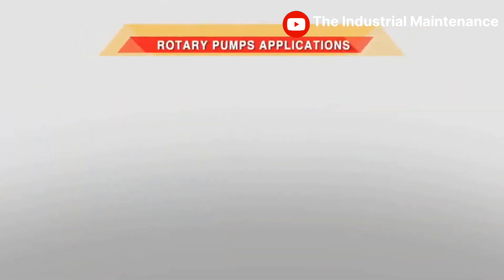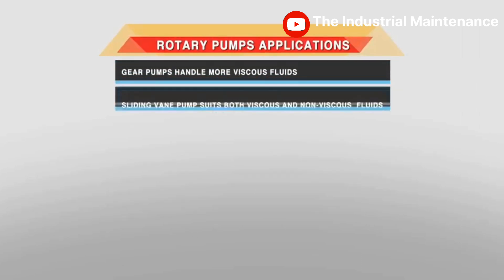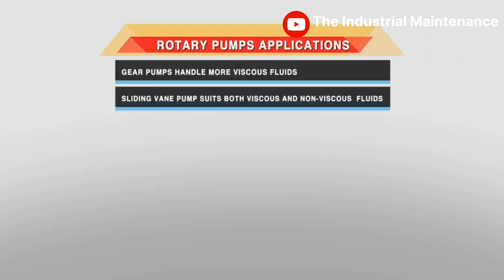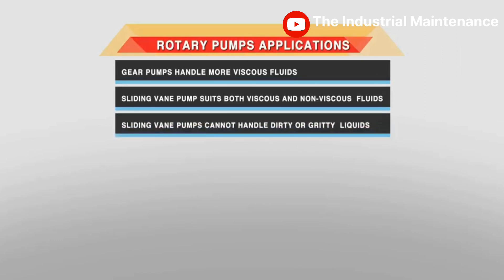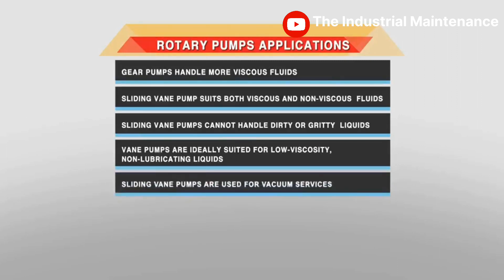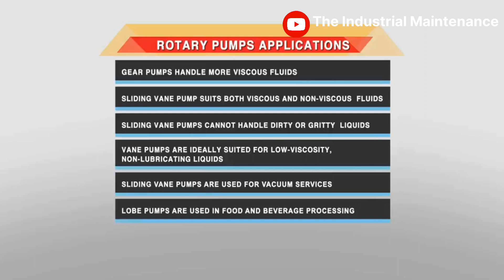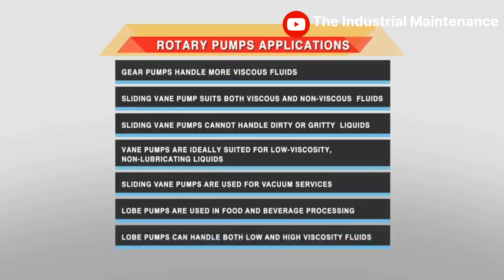Regarding applications of rotary pumps: gear pumps handle more viscous fluids. The sliding vane pump suits both viscous and non-viscous fluids, but cannot handle dirty or gritty liquids. Vane pumps are ideally suited for low viscosity, non-lubricating liquids and are used for vacuum services. Lobe pumps are used for food and beverage processing and can handle both low and high viscosity fluids.